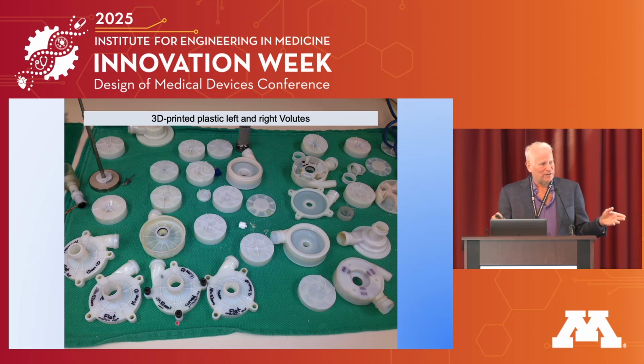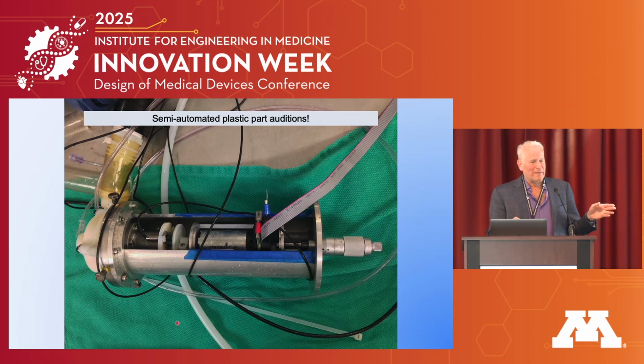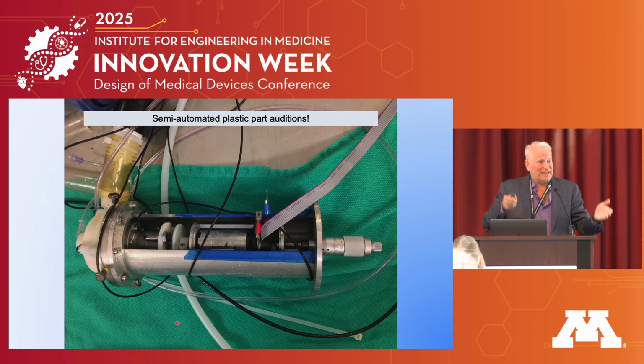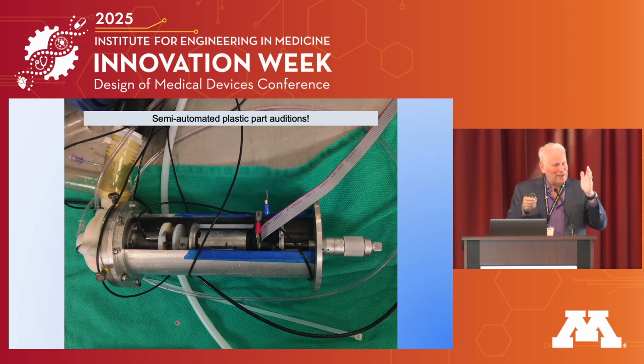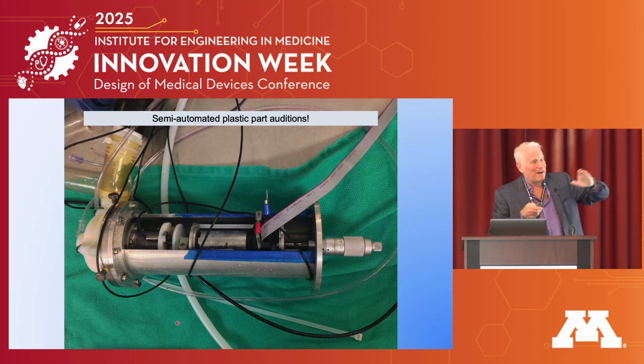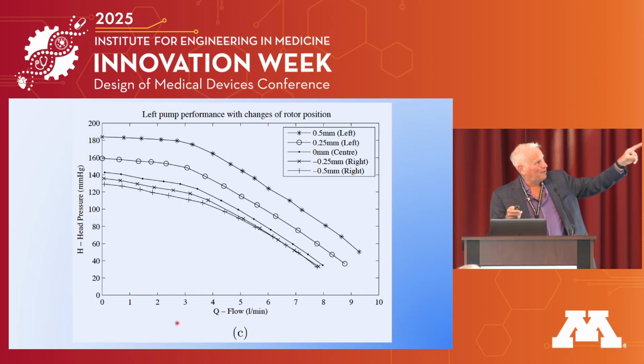And so we had all these parts and we thought, well, how are we going to test all these? One of the engineers stepped up and said, look, I made an automated tester, semi-automated. Put a volute in and a rotor, and it'll run through, using a pneumatic sort of pinch valve, every afterload at every speed and at every spacing. That's a micrometer on the end, because this impeller, this spinning thing, could drift to the left or right and did that several thousand times a second to balance the systemic and pulmonary circuit. Well, if we're making it so that the impeller performs differently depending on where it is, we got to check every spacing. But this thing generated all this data and then looked through, generated all these curves.